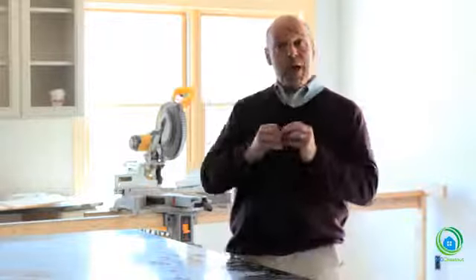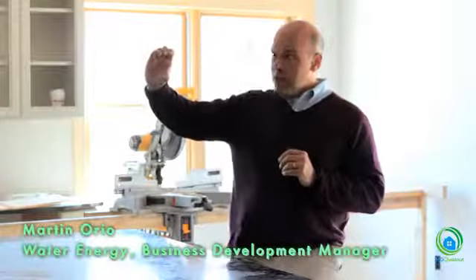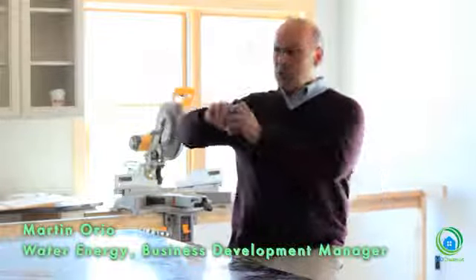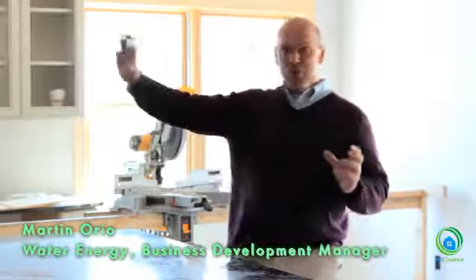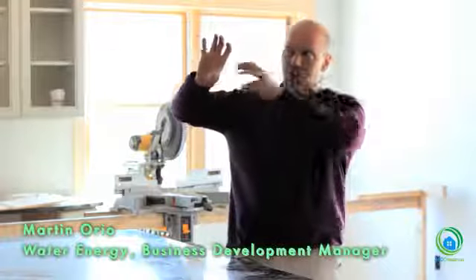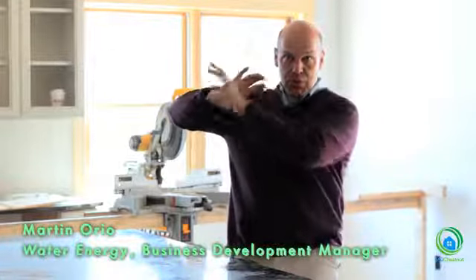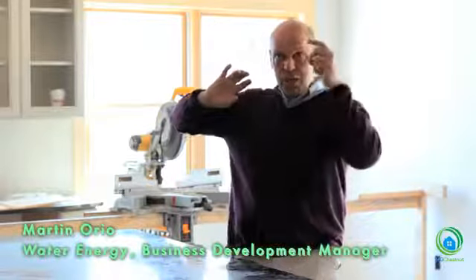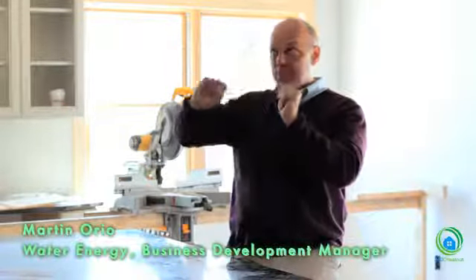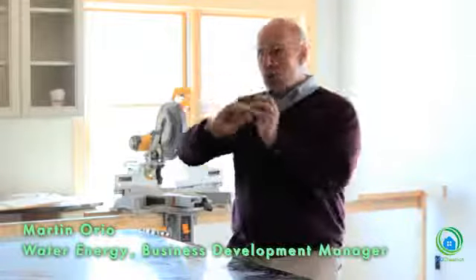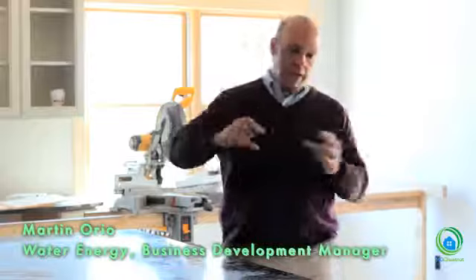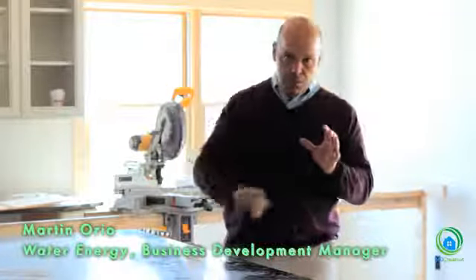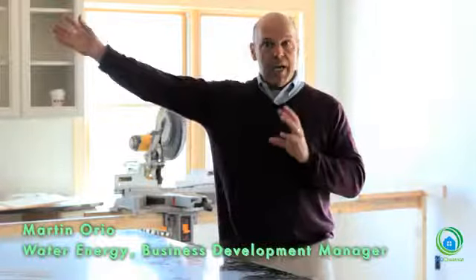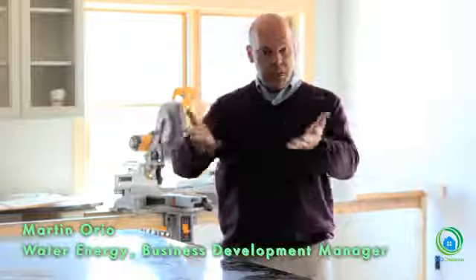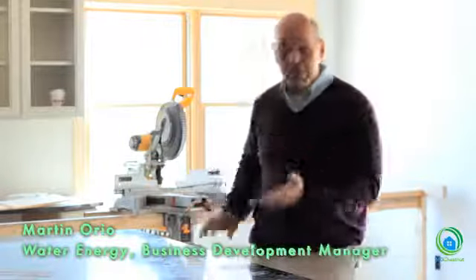So again, as I depart from that, I put in ductwork that's a little smaller than it really should be, I don't do my makeup air systems properly, and I increase the pressure in that ductwork. Well, now getting the heat off of that refrigerant coil with the airstream, I'm going to use more fan energy, and I'm going to have less comfortable delivery off of that coil. If I don't let it operate in that ideal space where it's moving the refrigerant from a gas to a liquid and back to a gas to move the energy, then I pay for that in inefficiency. And not only that, in longevity.